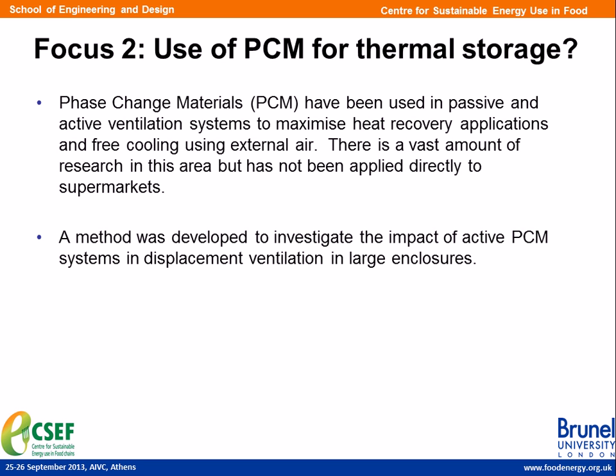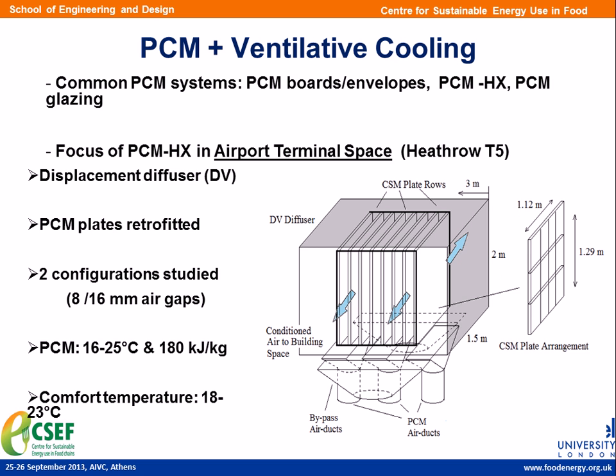In this AIVC conference, we've heard quite a lot about PCMs and how they have been used, and there is a vast amount of research in this area. We have developed a method at Brunel to investigate the impact of active PCM systems in displacement ventilation in large enclosures. This has been done for airport buildings, but we would like to investigate how it will apply to large supermarket buildings. So the focus is PCM heat exchangers. We've got a displacement diffuser with PCM plates retrofitted, in 2 configurations, 8 and 16 millimeter air gaps, and you can see here the temperature range and the physical characteristics of the PCM and the comfort temperature.